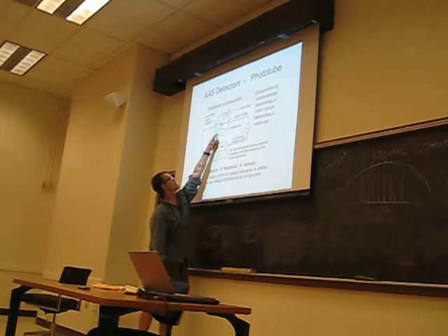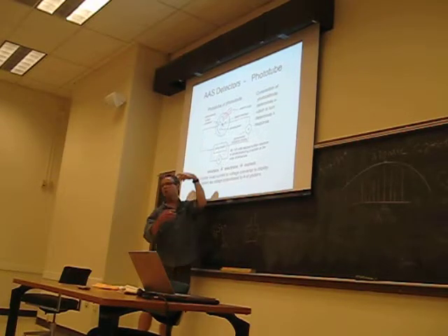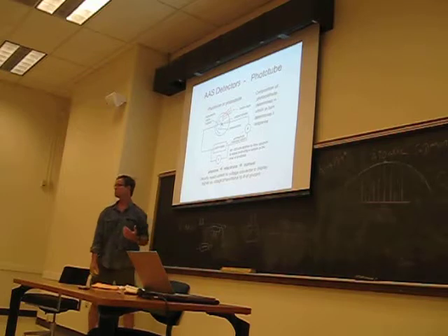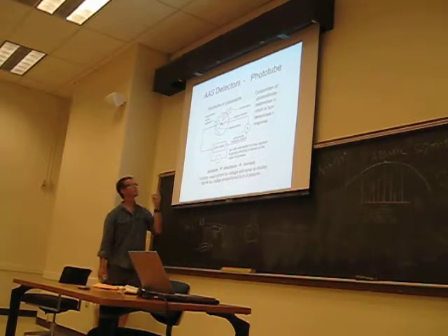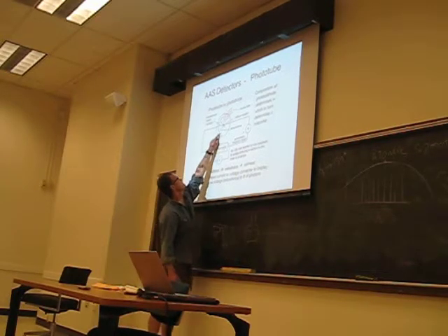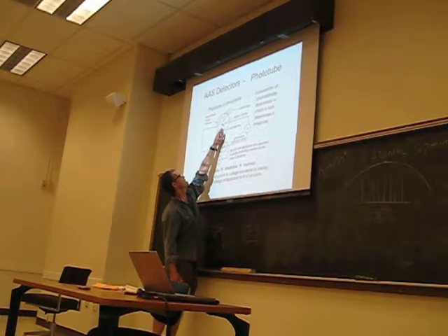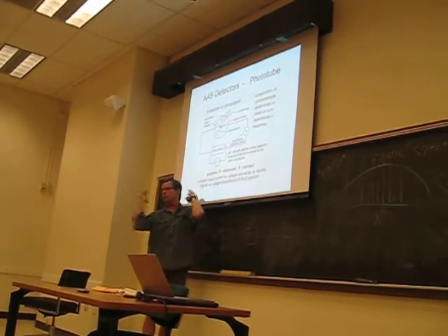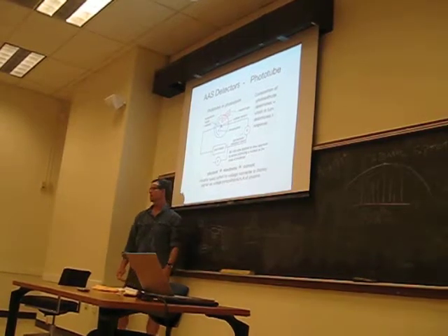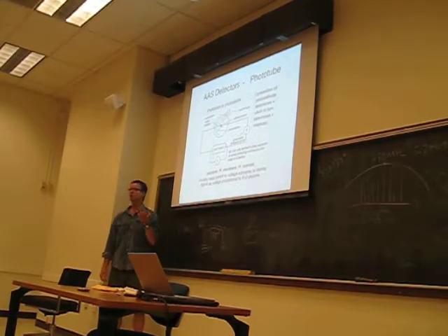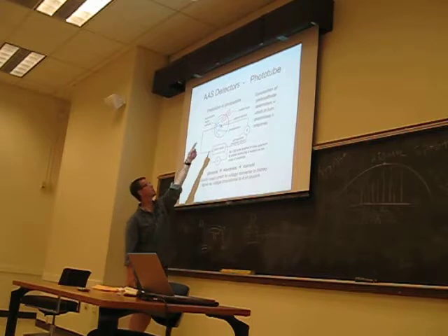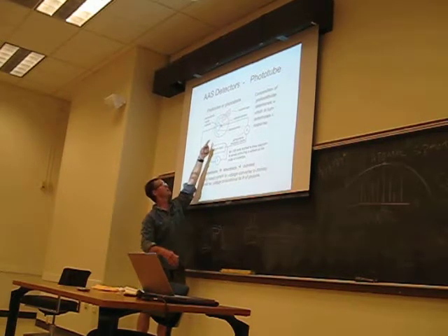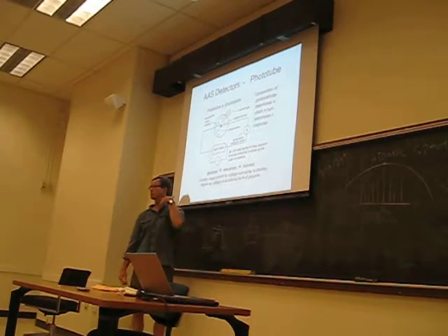When the photons strike that surface, it causes the release of electrons from that surface, because it's coated with electron-emitting material. The surface is functioning as a cathode, and in the middle in this cartoon is the anode, and those emitted electrons are attracted towards that anode. And that is then measured as a current. So the more photons that come in, the more electrons that get bumped out and get measured as a current, and you get a higher current.